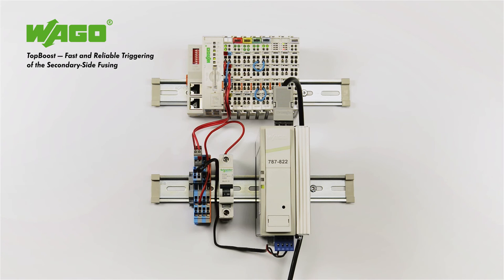The surest way to trigger a miniature circuit breaker is by using the top boost function. In this example, the 5 ampere power supply provides a current of 21 amperes for 25 milliseconds in the event of a short circuit. This short circuit current is sufficient to trigger the magnetic section of the fuse in the C2 miniature circuit breaker for a brief moment. These options are limited, however, by the cable length. If the application is spread over too great a distance, even the top boost may not be able to provide enough current through the cable to the miniature circuit breaker. This is another situation in which an electronic fuse would be the best choice.